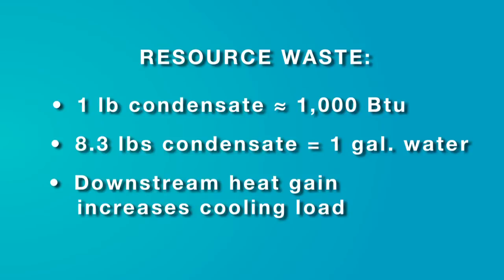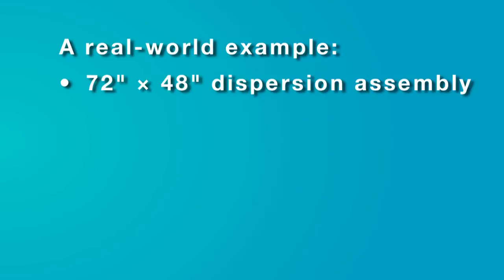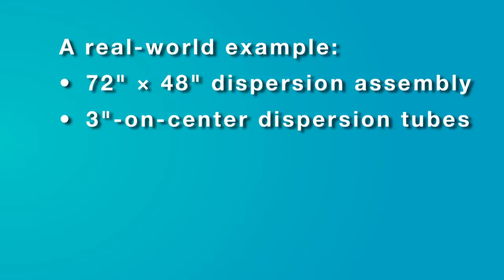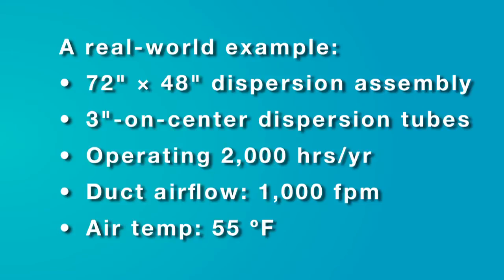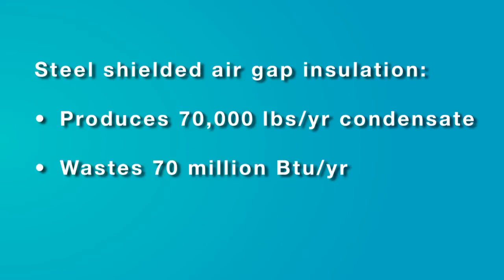What are the real-world implications? For example, a 72-by-48-inch dispersion assembly with 3-inch on-center dispersion tubes that are insulated with stainless steel shielded air gap insulation and operating 2,000 hours per year in a 1,000 feet per minute 55-degree duct airstream will produce approximately 70,000 pounds of condensate and waste approximately 70 million BTUs per year.